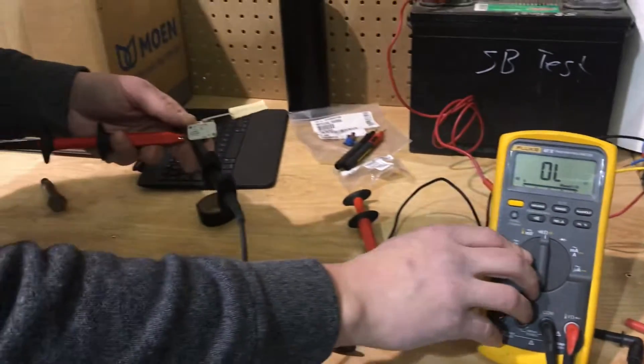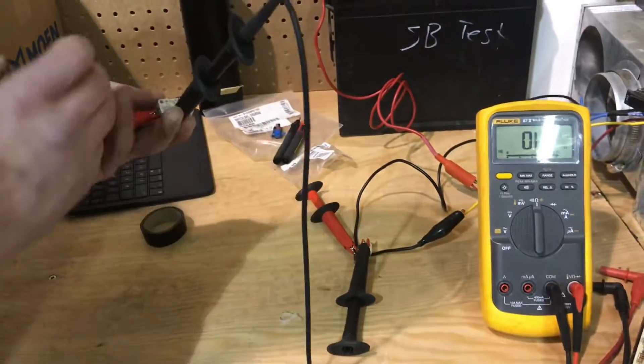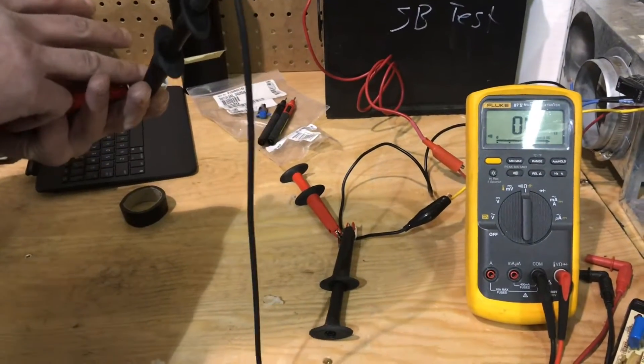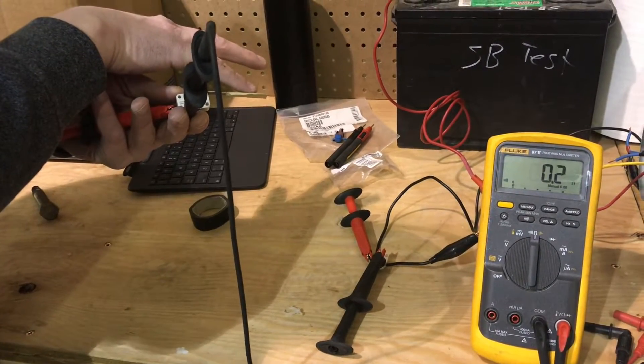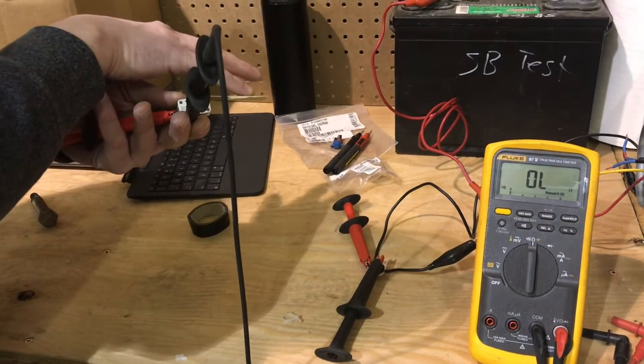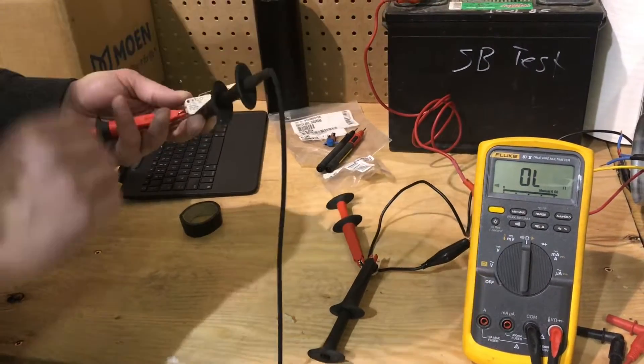When you're checking the sail switch, you're going to connect to each terminal. This switch is normally open, so you're not going to hear anything until you close the circuit. That indicates a good switch. If you've tested that, you can eliminate that from your issues.